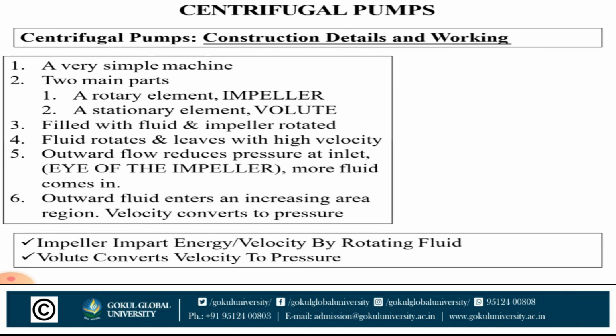Centrifugal pump construction details and working. A very simple machine with two main parts: a rotary element, the impeller, and a stationary element, the volute. The casing is filled with fluid and the impeller is rotated. Fourth, the fluid rotates and leaves with high velocity. Outward flow reduces pressure at the inlet eye of the impeller, so more fluid comes in. And last, the outward fluid enters an increasing area region, and velocity is converted to pressure.